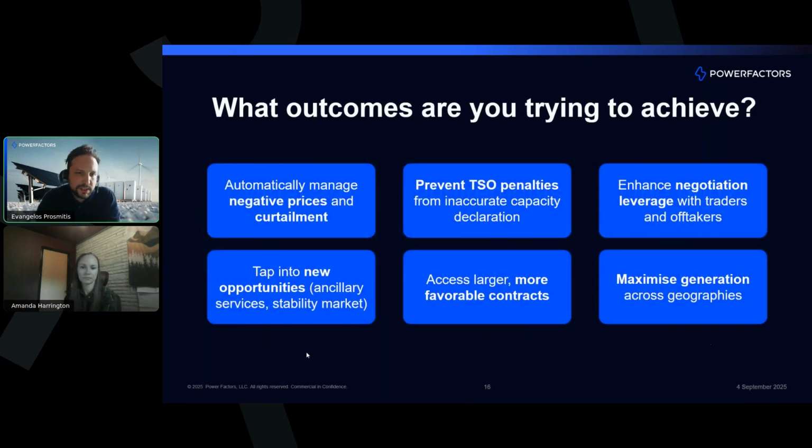Yes, at the beginning, we're seeing several challenges, market-wise and price-wise. We're seeing many days of negative pricing, for example. So all the owners that have standalone wind and PV assets need to take care of the negative electricity prices. There was a peak, if I can recall correctly, I don't recall the number of hours, but in Germany they had a negative peak of negative pricing. So collocating a BESS asset in an existing wind or PV plant secures the owners so that they will not need to pay or address any negative electricity pricing issue, by charging the BESS while the negative pricing occurs.